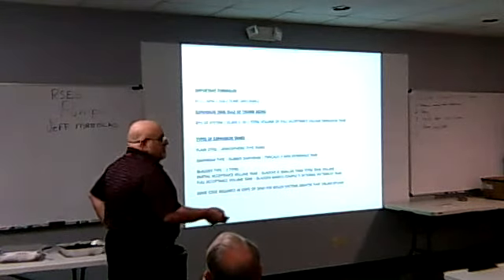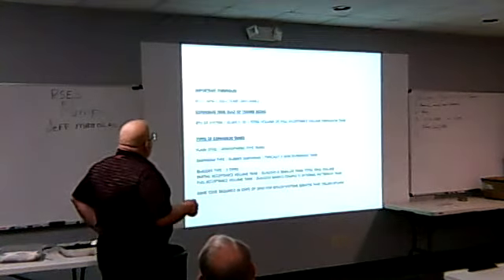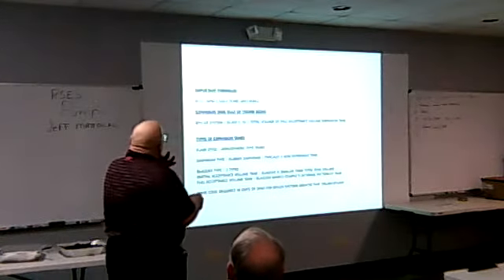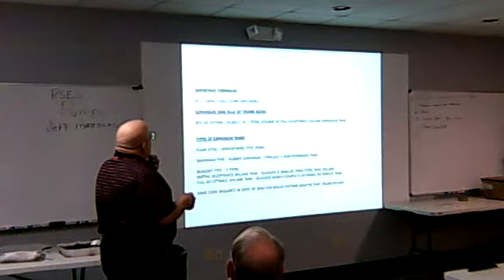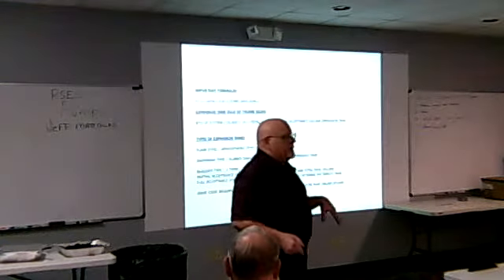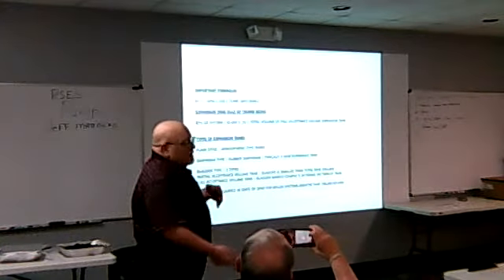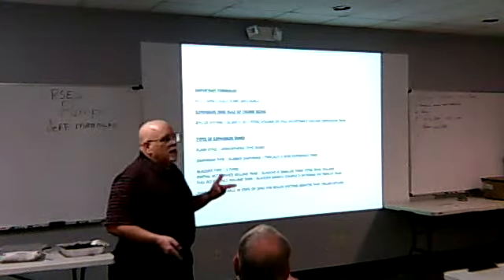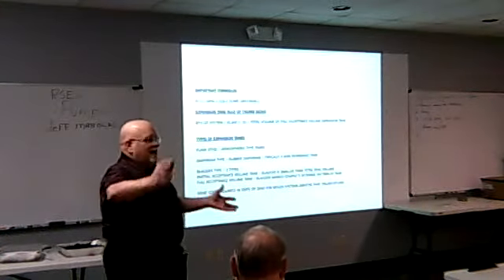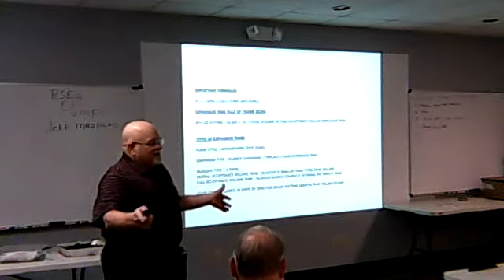Okay, expansion tank. Well, I forgot to mention, this is a really important equation. He was bringing this one up earlier. This is why I love hydronics, plus or minus 50%. A lot of people don't get that. Your BTUs are equal to your GPM times 500 times your temperature difference. We typically design for a 20 or 30 degree delta, and 20 is pretty standard. The beauty of hydronics is that most hydronic fan coils and fin tube are designed to run between about 3 feet per second velocity and 8 feet per second velocity. As long as I stay in that range, the unit is going to perform correctly.